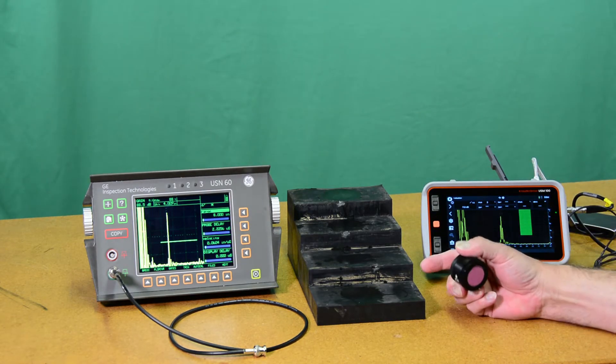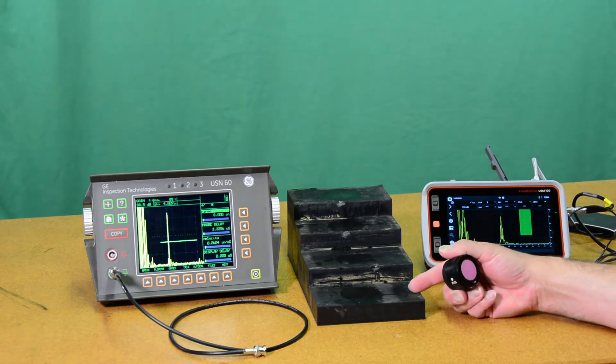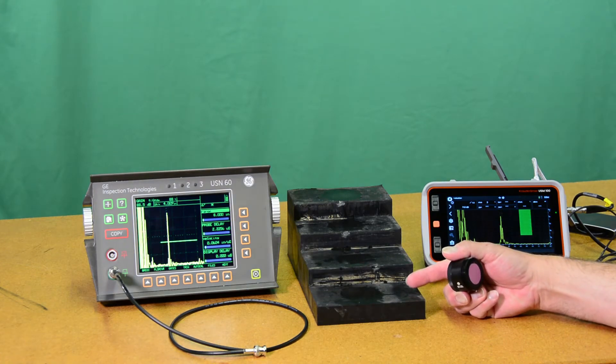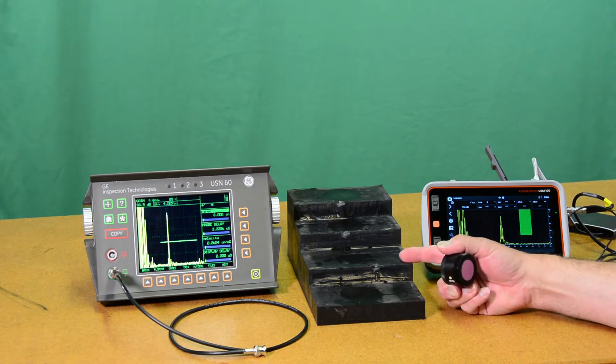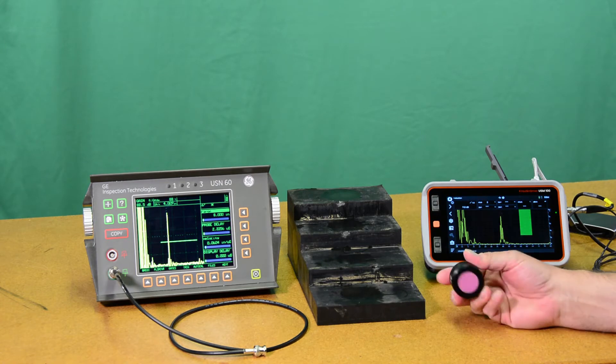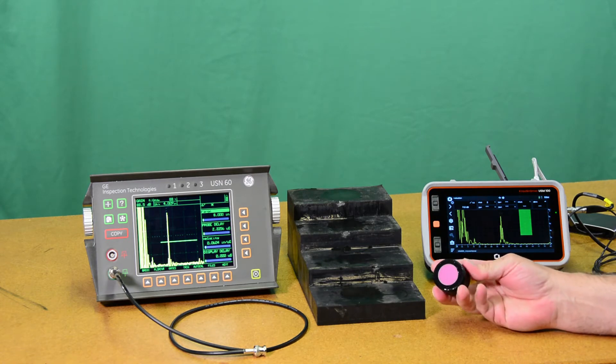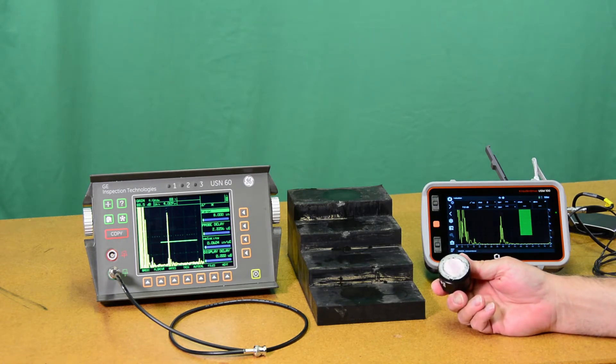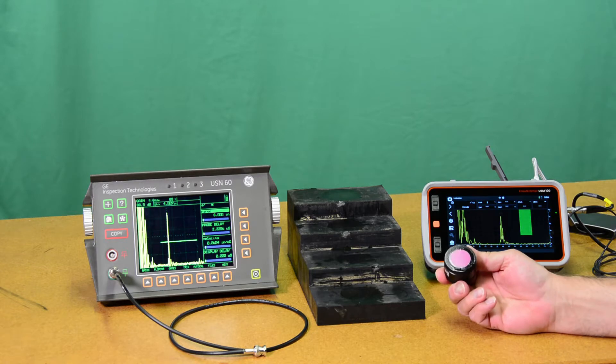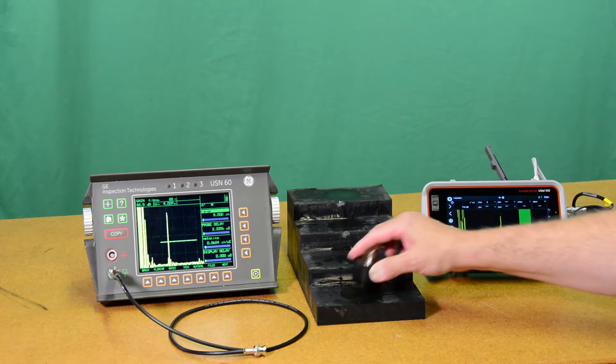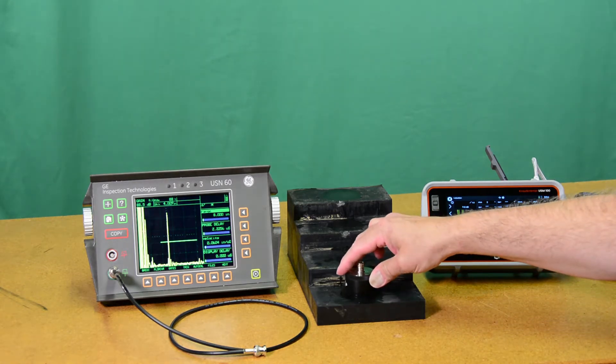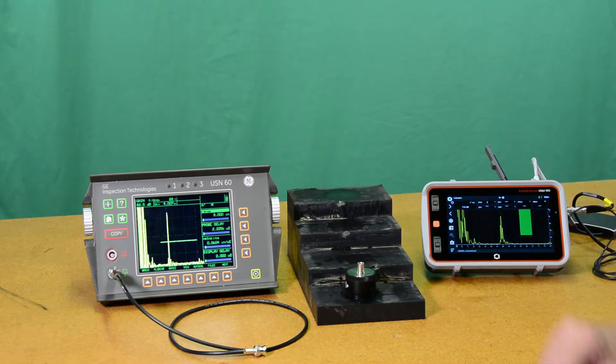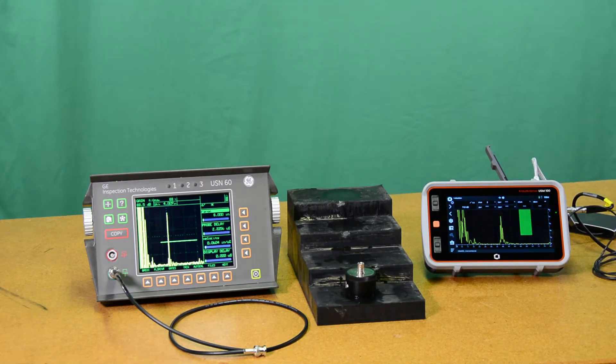In this case I have a rubber step block here with steps at 1 inch, 2 inch, 3, 4 inches and I have a very low frequency probe, a 500 kilohertz probe, 1 inch diameter that's well suited to penetrating through this very attenuative rubber material.